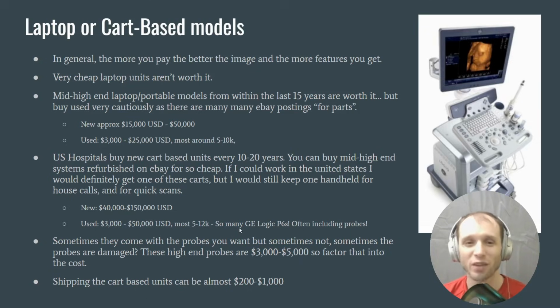Oh, they're so cheap, and there's so many GE Logiq P6s. The GE Logiq series is the sort of general use ultrasound machines. Those would make an excellent choice, and for these prices, they often will include probes. Now, sometimes they come with the probes you want, and sometimes not, and sometimes the probes might be damaged, right? Or they might not last very long because they might be used. Keep in mind, these high-end probes are $3,000 to $5,000 on their own. So they're basically the same price as a wireless probe, maybe even more. So factor that into the cost of buying one of these.